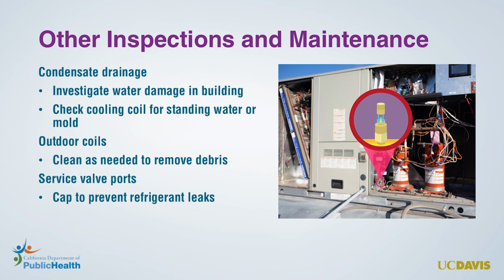When inspecting the air filters, inspect the cooling coil to check for any standing water or mold, which indicates a drainage problem and can be a source of indoor air pollutants. HVAC systems transfer heat outdoors with an outside coil and fan. The air moving over the outdoor coil is not filtered and can carry debris. Check your outdoor coils periodically and clean and remove debris as needed.